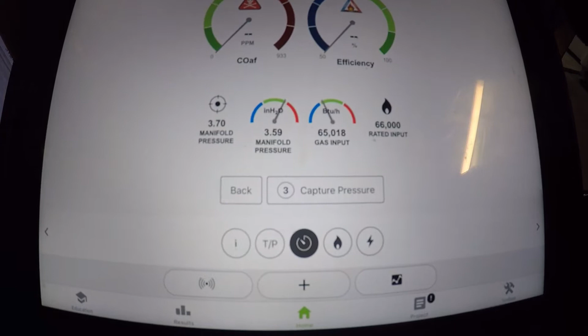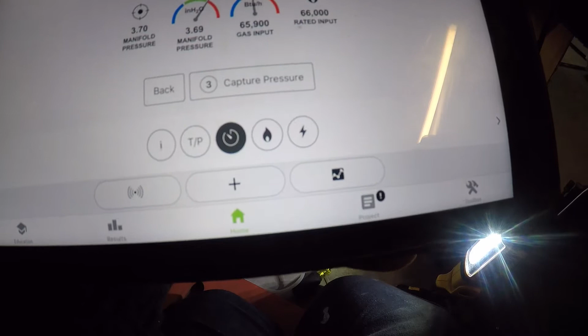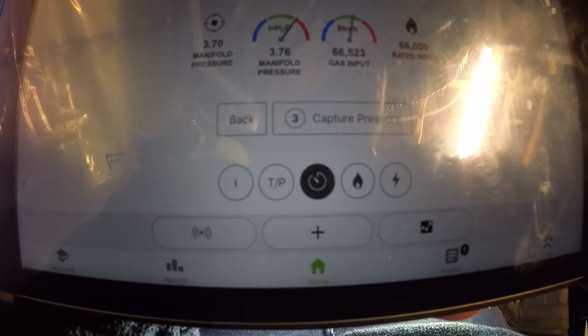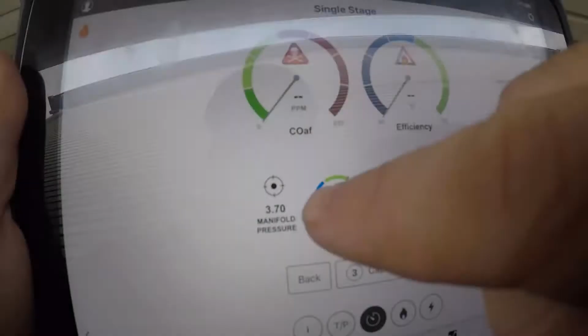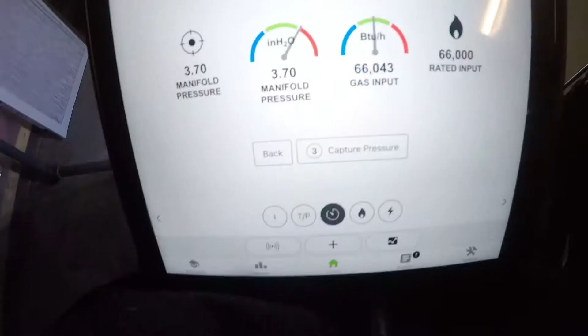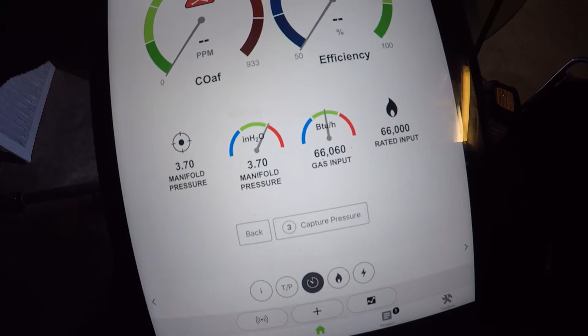So technically my pressure is 3.58, so I'm going to go up 12 points. Look at my input, 3.68, 3.67, just shy of 66,000. I'm going to go a couple points above. 3.7 on the dot. See how it's just pressure is 3.7. So let's go inside and dial that gas valve in so that we get the proper input. 3.70, 66,000. That is by far one of the most important things you could do for this furnace. Okay?